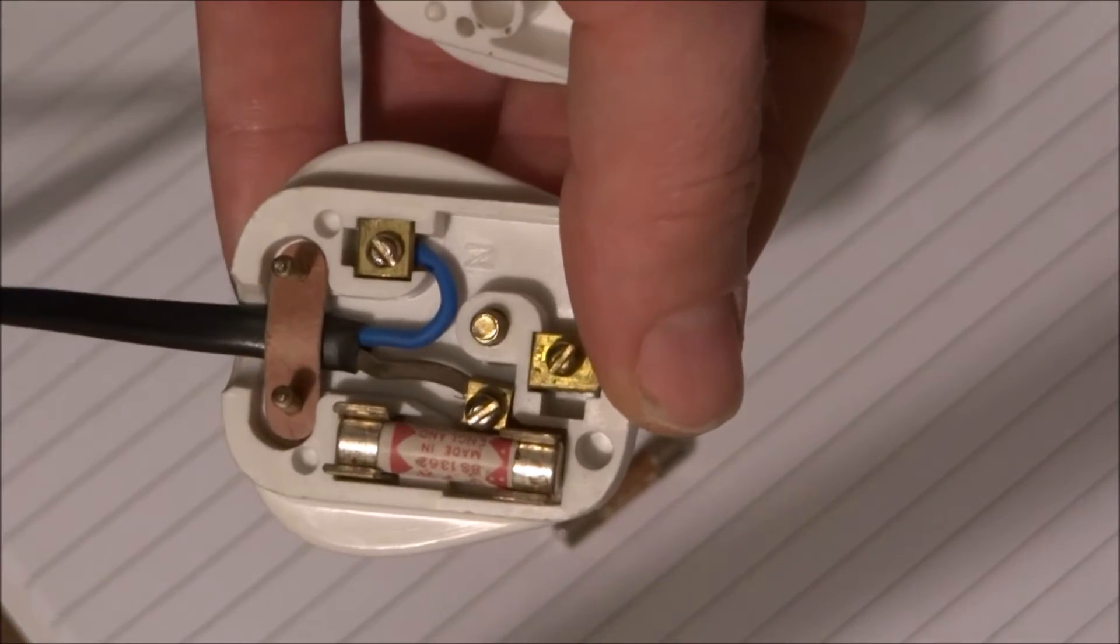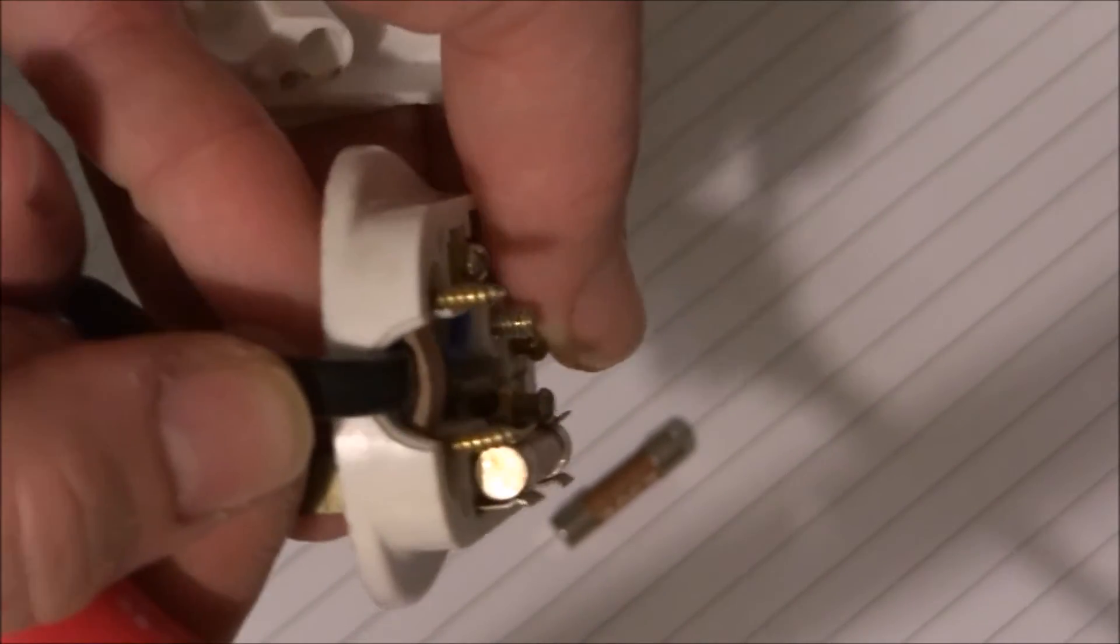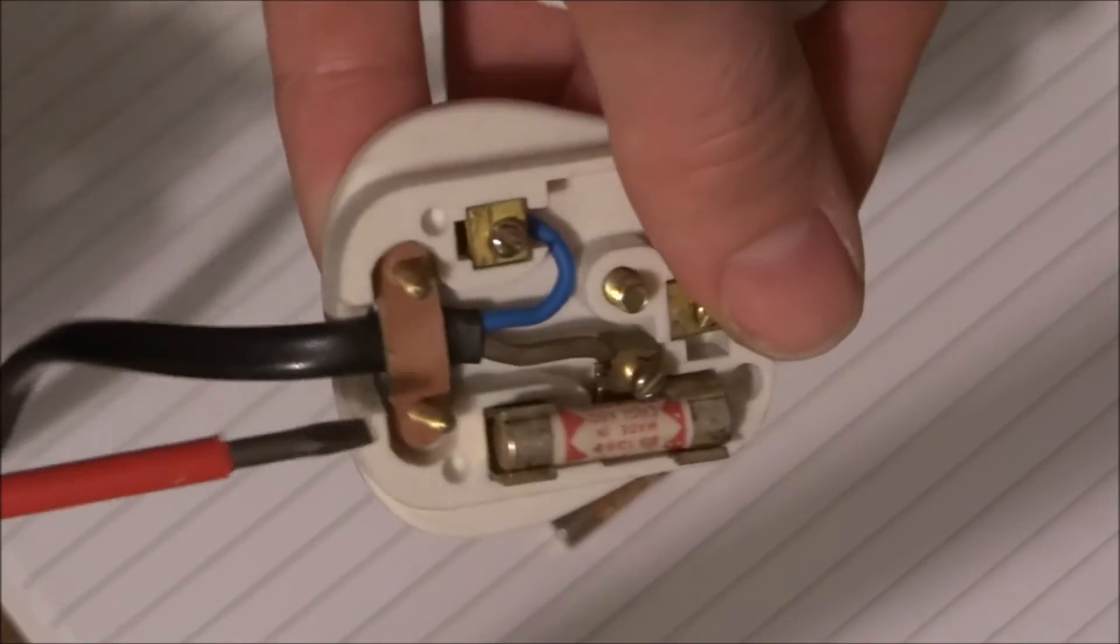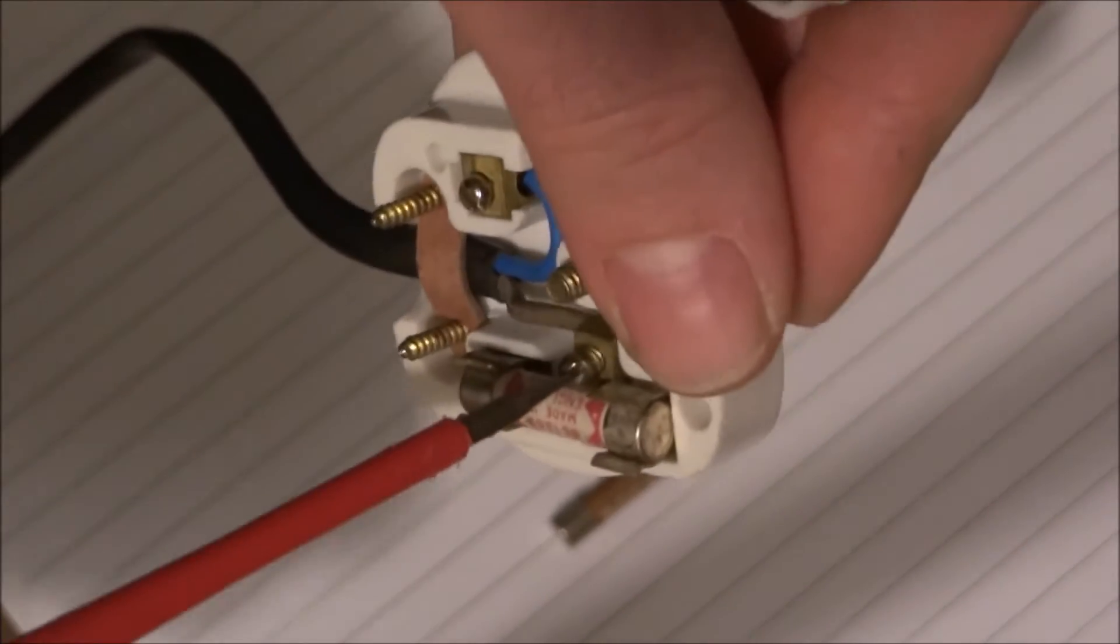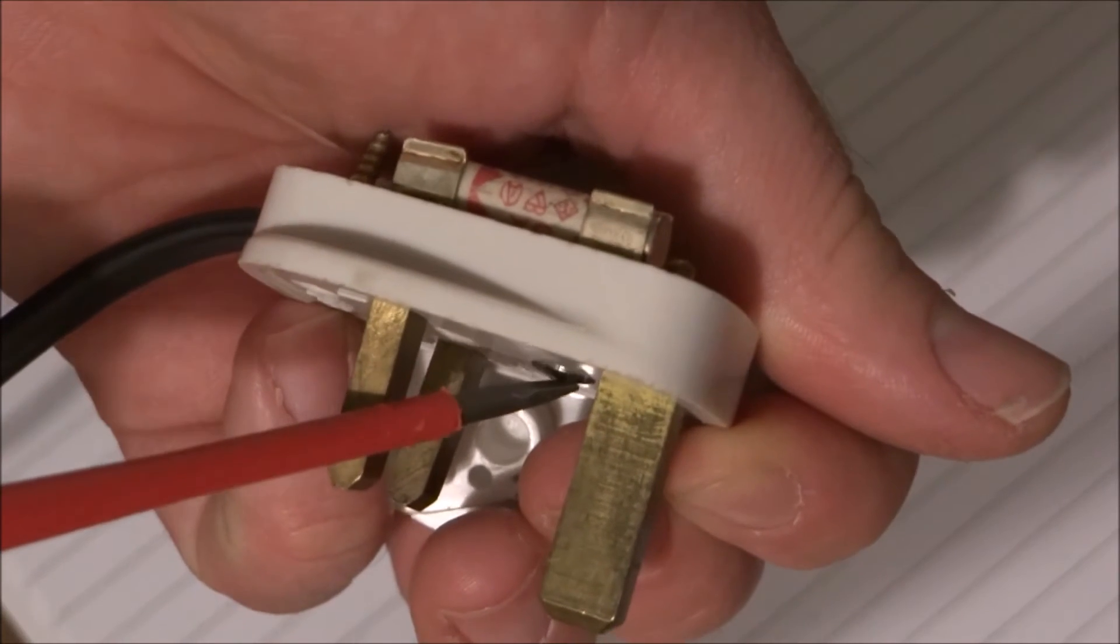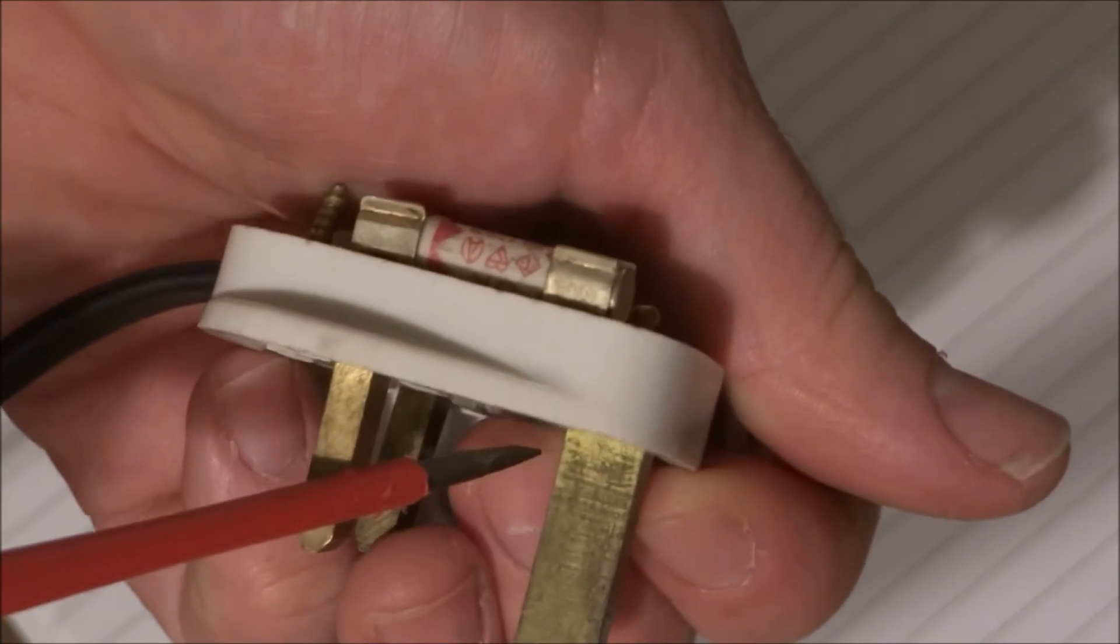However, the plug itself is fairly substandard. It's got a very flimsy paper cord grip compared to the better ones of the era that had a thick paper cord grip. These screws have got like a dome head on them which aren't very nice to work with, and also underneath, the center screw here actually protrudes even when it's done up fully, maybe about a millimeter, which would actually stop this from being completely fully inserted into a socket. So it's a bad plug and I'm going to get rid of it, it was just for demonstration.